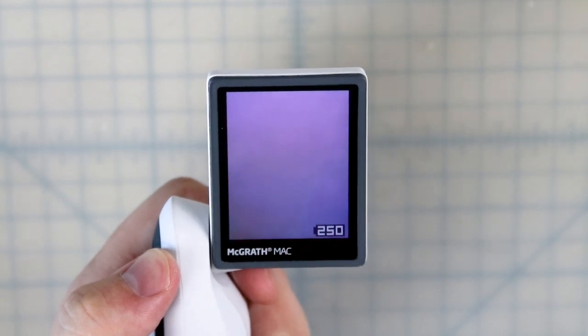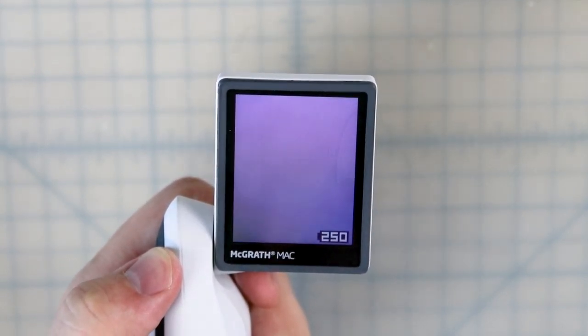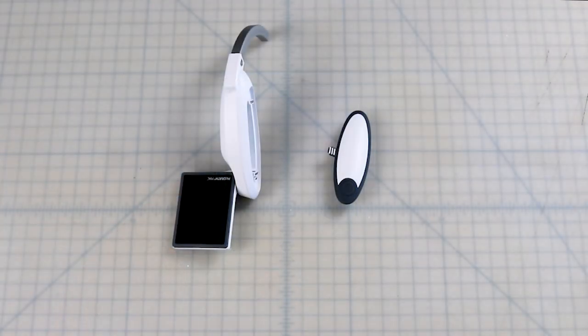Use your battery pack as normal, and when the battery pack is depleted, simply perform the process again. One additional question that I did not explore is: can the 250-minute counter be reset without replacing the battery cell? That is, how much time is left on the battery when the counter reaches zero? Can one simply reset the counter and get another 250 minutes? Because the replacement battery cells are so inexpensive, and blindly resetting the counter might lead to the device shutting off during intubation, I chose not to explore this concept.